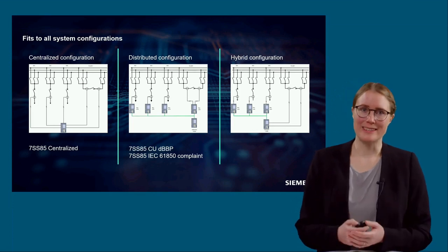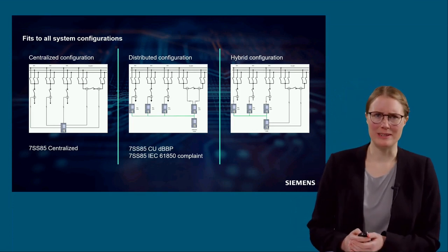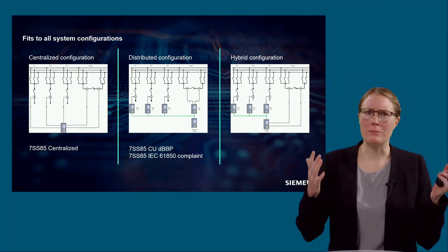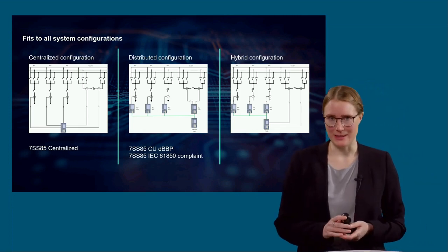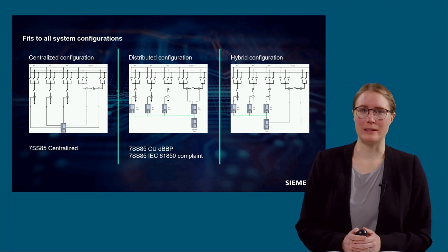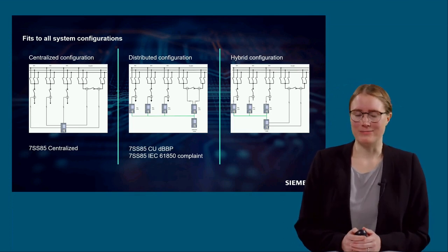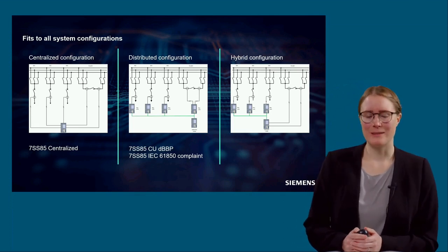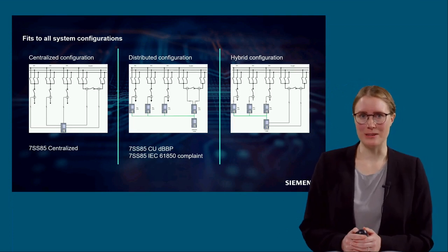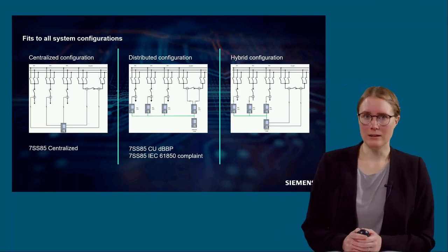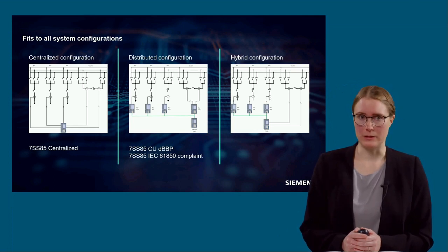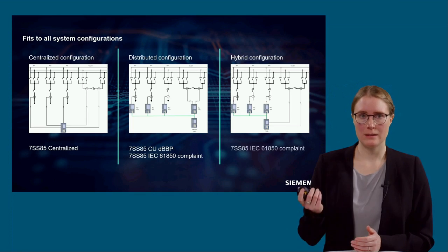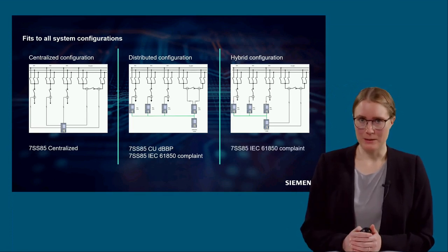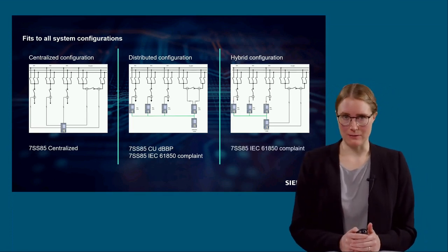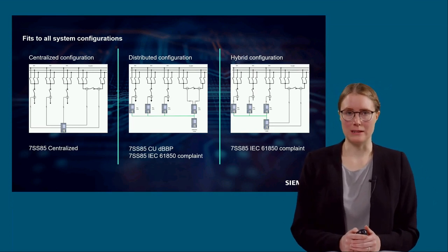In this case, the central unit is no longer the overall brain of the system. The bay units have some intelligence as well. You can maybe imagine it like this. With the 7SS85CU solution, the engineering effort is lower, and you can realize bigger busbar systems with more measuring points. For the hybrid setup, you must use the 7SS85 IEC 61850 compliance solution.